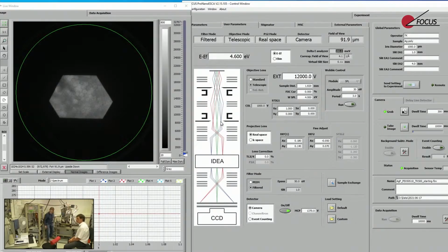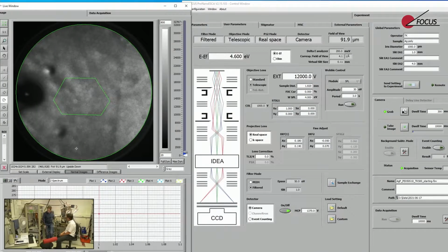So my aim is to close it to about 1/3 of the field of view, or a little bit more. But I will close it later to this size. And now we can move the sample underneath and thereby choose the region we would like to investigate in momentum space, and close the iris aperture again. So actually we are sitting right on this left side crystallite pretty nicely in between the spikes and not too close to the grain boundary.